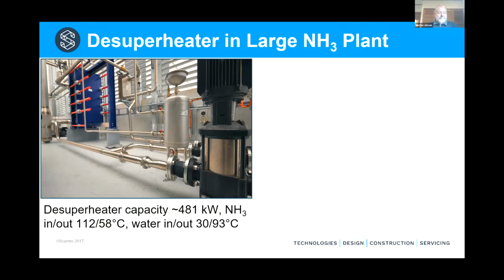And here you see the desuperheater is of the plate type, and you can see both heat exchangers here. The blue one is the ammonia water heat exchanger, and the other one next to it, that little water-to-water heat exchanger, is the one I showed in the previous diagram. This is to create a closed water loop for the desuperheater itself, so we avoid that it fouls up. The pump in the foreground is the pump that circulates the water through the closed circuit.